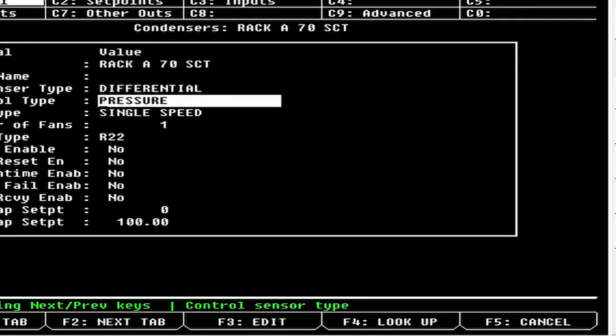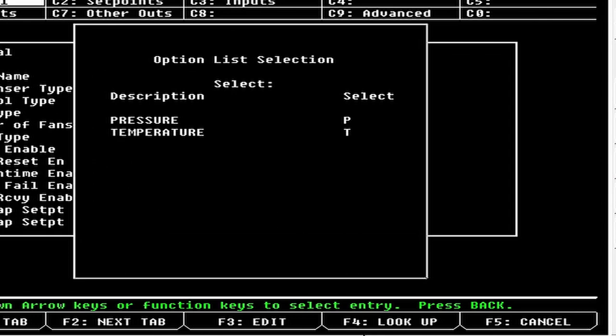Next we have Control Type. If you hit F4 Lookup, you have two options: Pressure or Temperature. You could use a temperature sensor strapped to the drop leg, but it's going to be kind of laggy. You want to use Pressure, and in Differential mode it's going to automatically convert the pressure to saturation temperature, so we're controlling off saturation temperature.